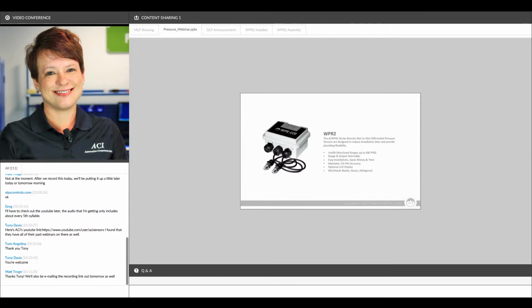Now I'd like to shift over and talk about the products that we make for wet media and other harsh media applications. And this is going to include not only water, but also chilled water, steam, refrigerant, ammonia, and other harsh media. I'm going to start out with our WPR2. This is the newest addition to our pressure line. It is a differential wet pressure transducer, good for pressure ranges up to 0 to 300 psi-D.